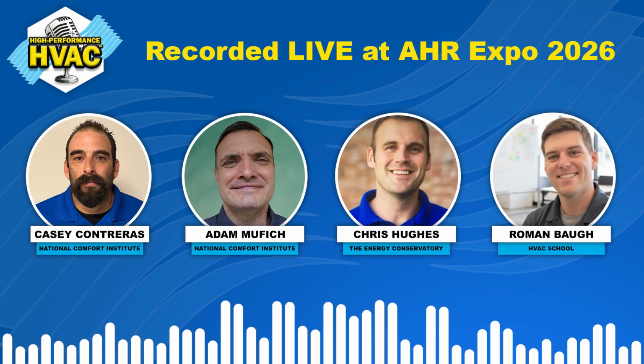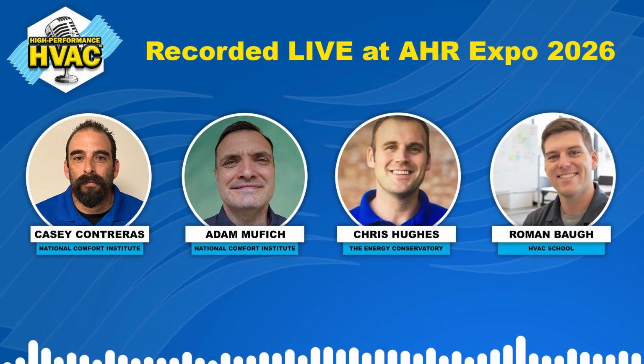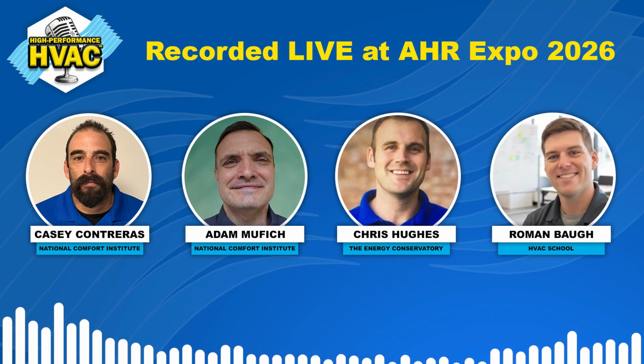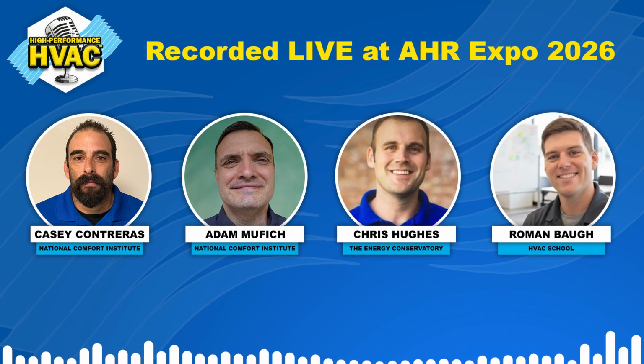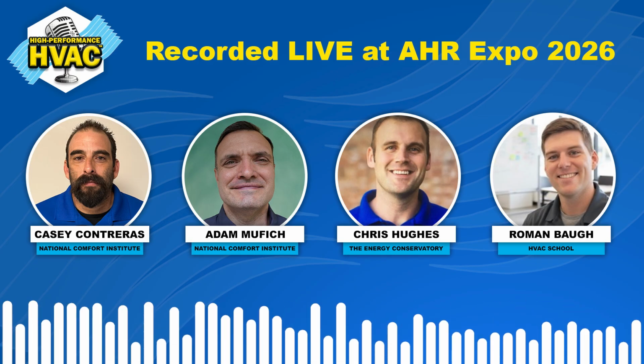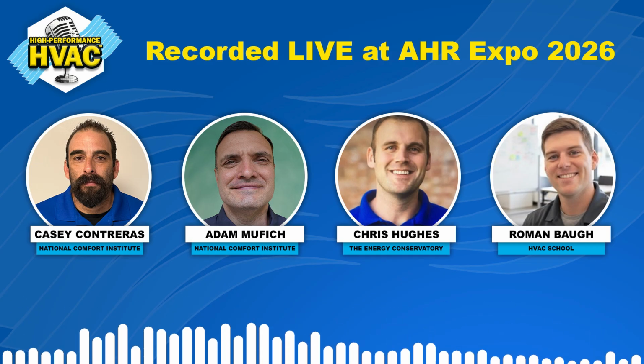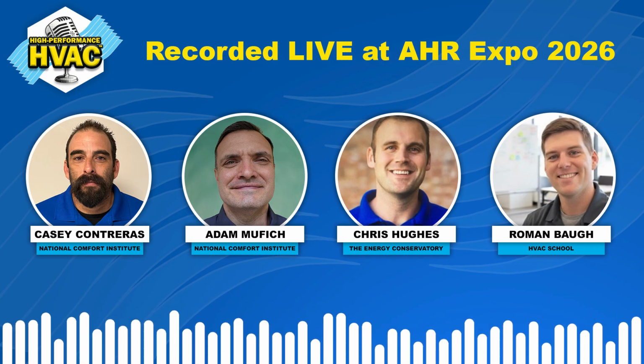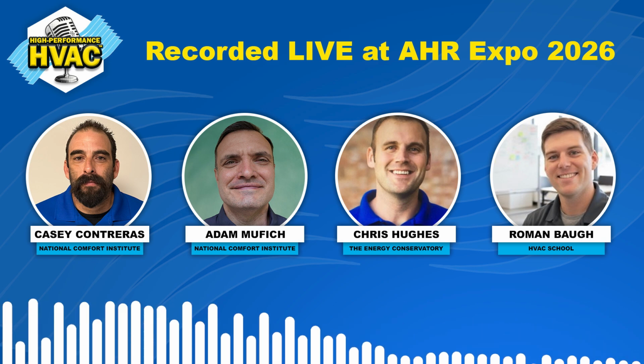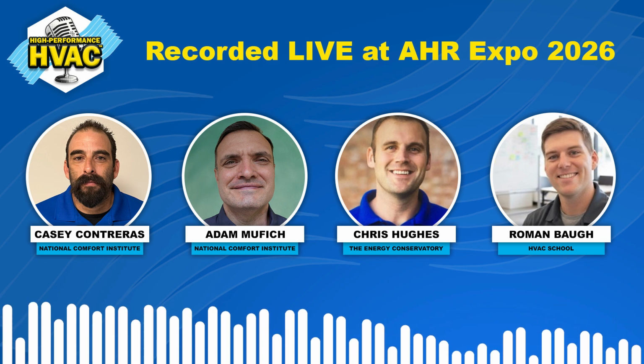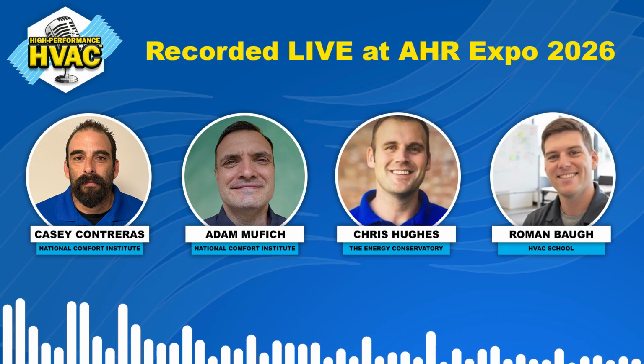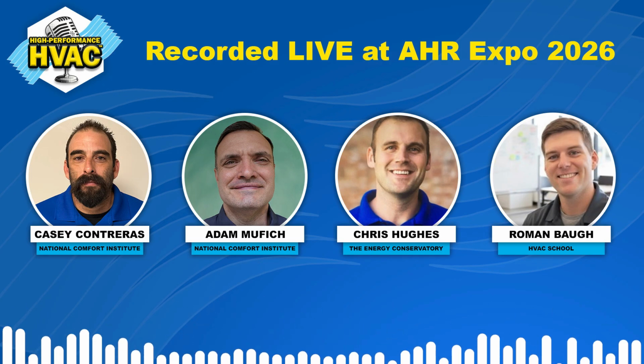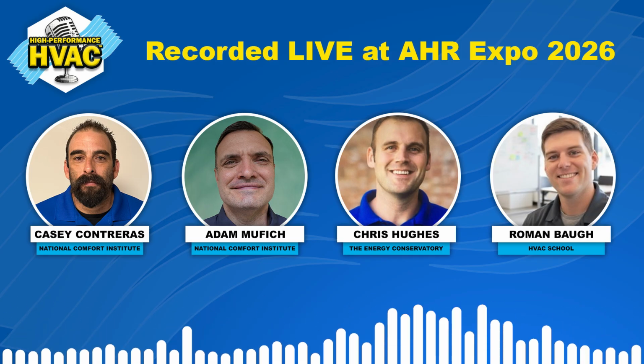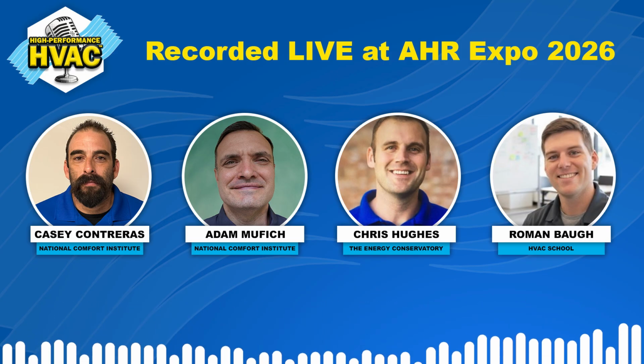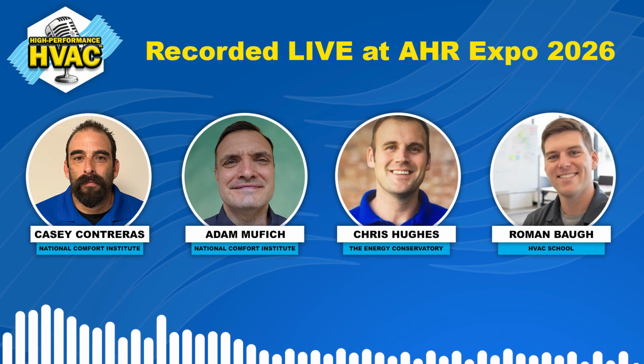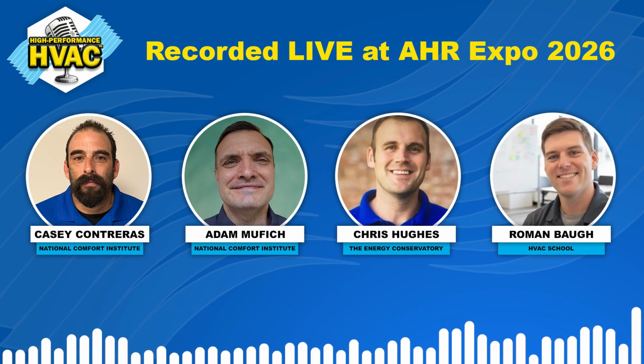You got a lemon. Well, obviously, maybe. That's a conversation maybe I'll have at this show at a different time tomorrow morning. I was talking to Ty about it, and it seemed like every pump, I don't want to generalize, but every one we were looking at all had the same 32-degree threshold. You gotta crank it up inside and then bring it out. Well, it's something I think that should be discussed, and what I'm generalizing is saying maintenance about heat pumps in cold climate while it's cold outside should be a discussion. Jim Bergman made a video about pulling a vacuum when it's freezing outside and the difficulties of that. And I'm experiencing this refrigerant recovery in cold climate, and I've got complaints.